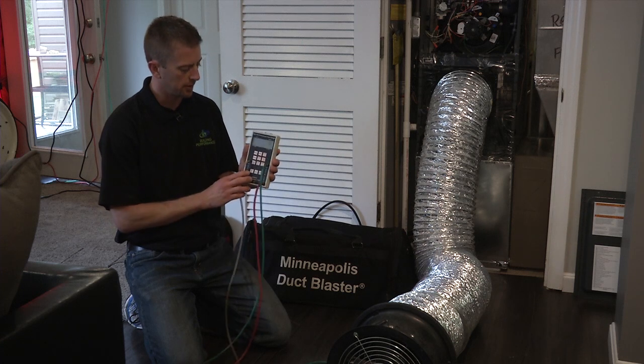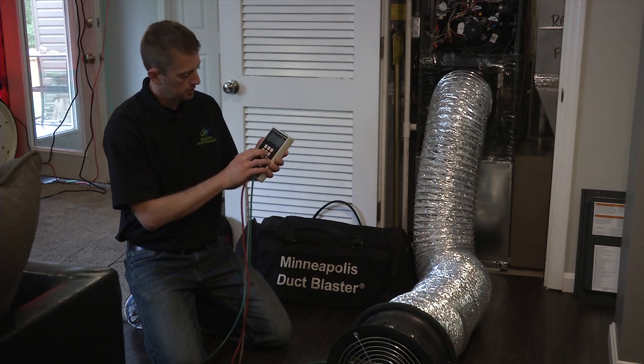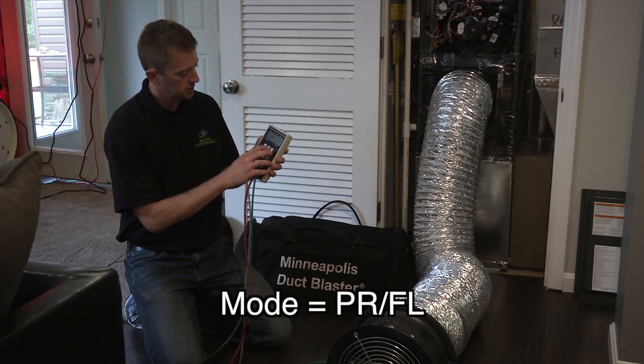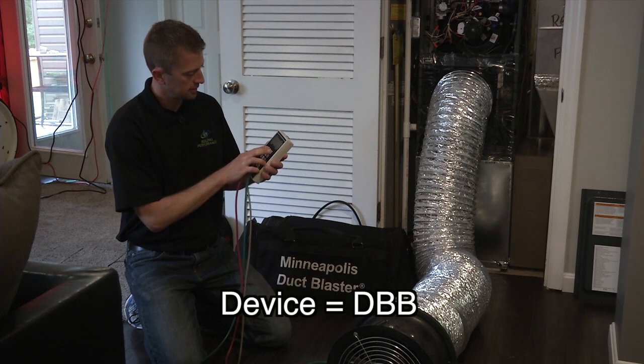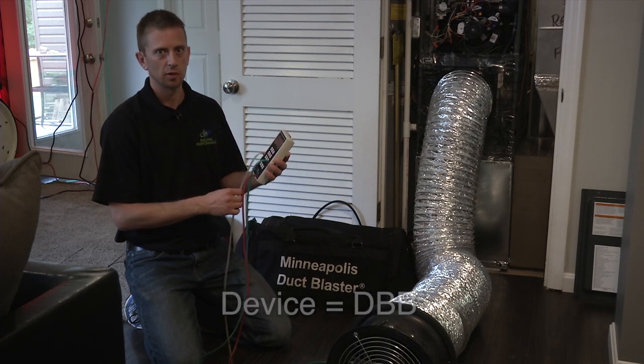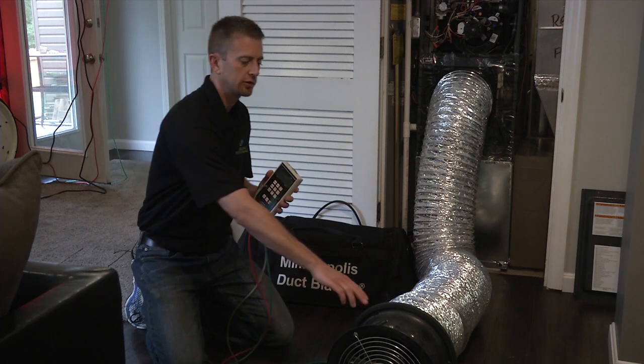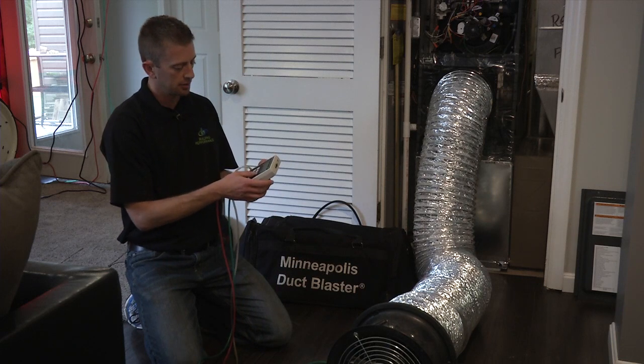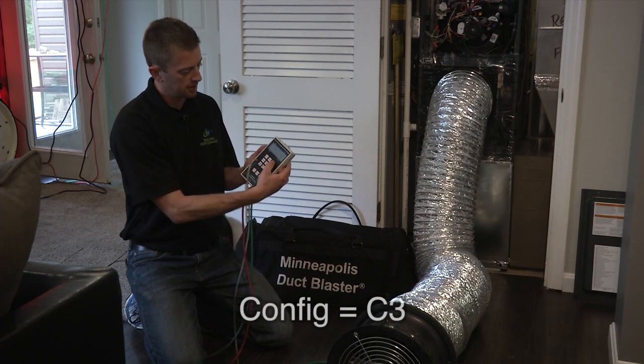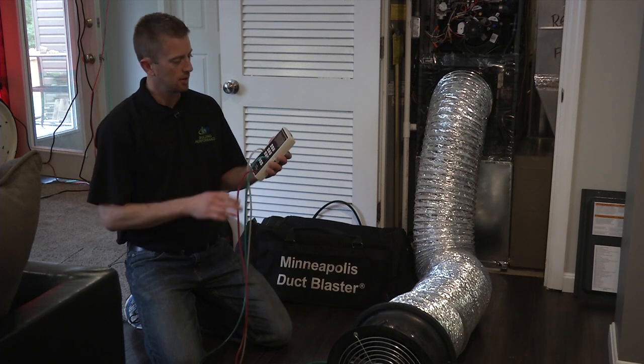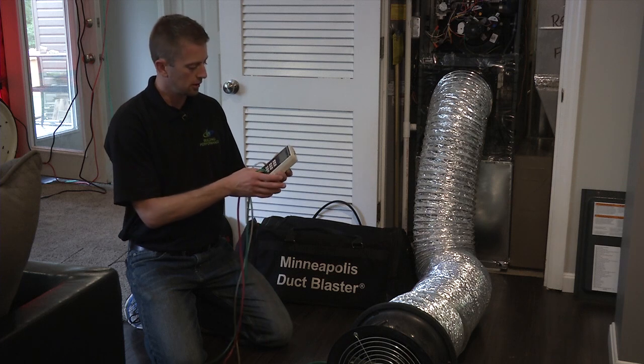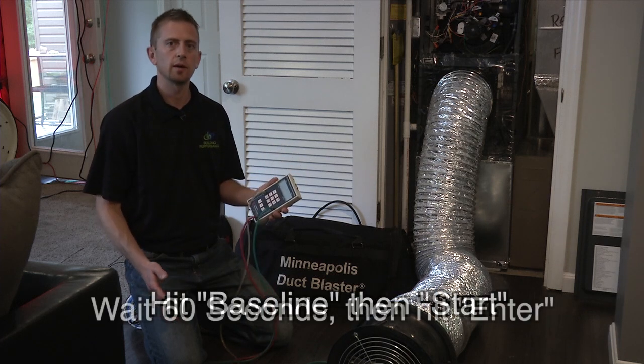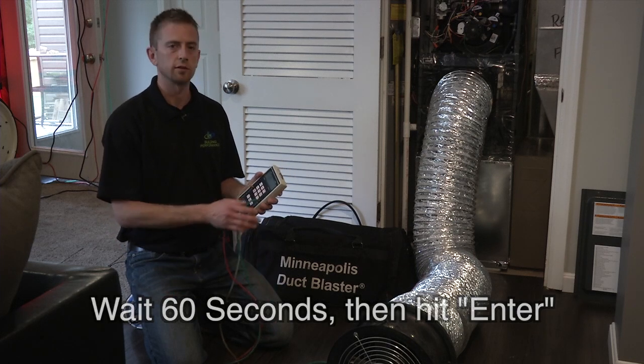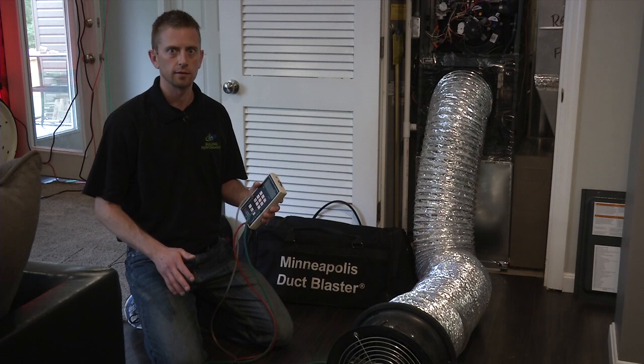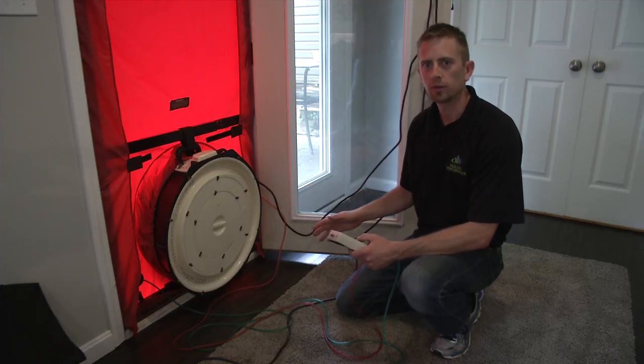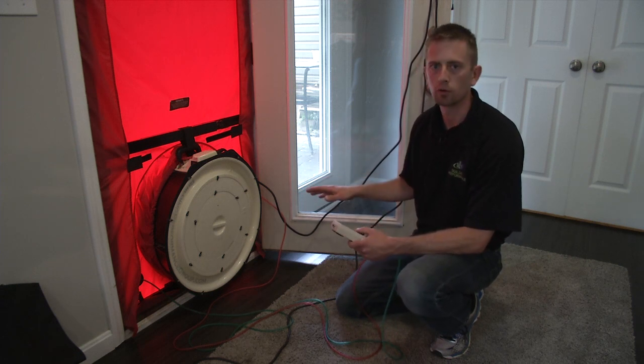You're going to turn on the gauge. Then you're going to hit mode until you see pressure flow. Then you're going to hit device until it says DBB at the top. That's Duct Blaster B. Once this is set up, you need to make sure that your ring setting's correct on the Duct Blaster. I always default to ring 3. So you hit config until it says C3. Now it's set up and I can baseline the gauge. All I do is hit baseline start, wait about 60 seconds and hit enter. That baselines the equipment and gets me ready to do the duct leakage test. Alright, so now that we've got the Duct Blaster set up and baselined, we need to go to the blower door and do the same thing.